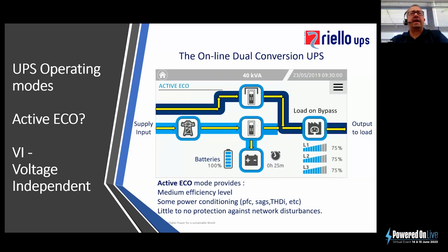So it's effectively working like an active power factor corrector or a power conditioner in terms of power factor correction, SAGs, THDI, and so on. What it's doing is, if any nastiness is being produced by the critical load, that's not being reflected onto the grid, whilst at the same time the UPS is subsidizing that voltage or that quality of waveform. Now, the benefits of this, again, efficiency sits somewhere between the eco mode and the online mode. However, this time, you've got that power conditioning. But the downside, because it's still directly connected, you still have little to no protection against network disturbances. And so, again, it's great to have it, but it's not a favored solution.